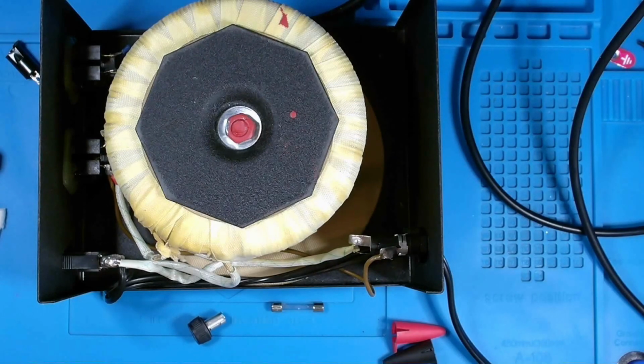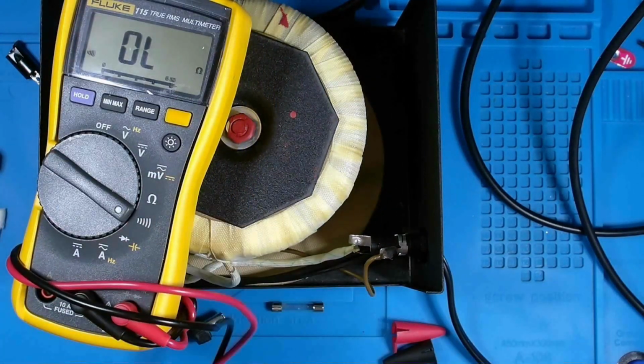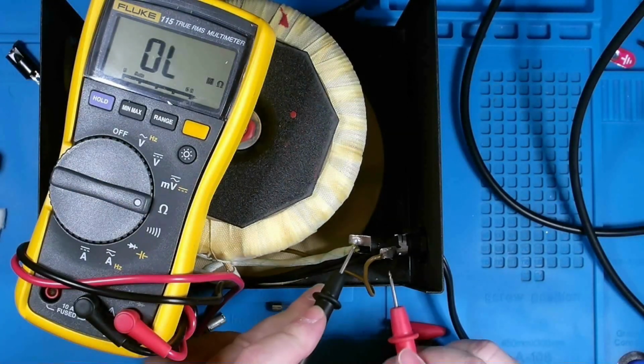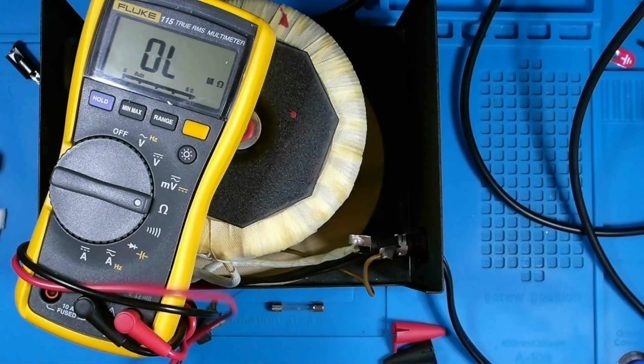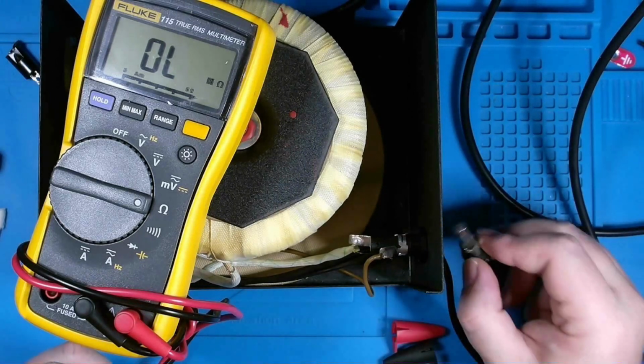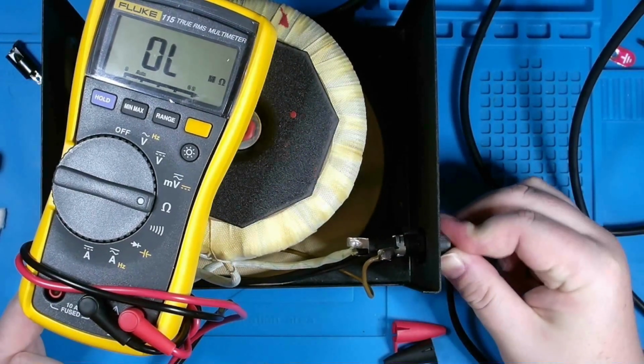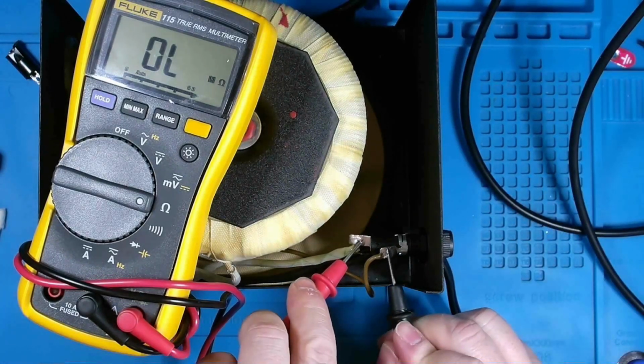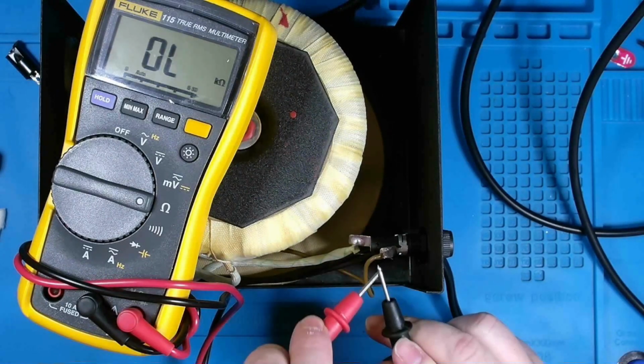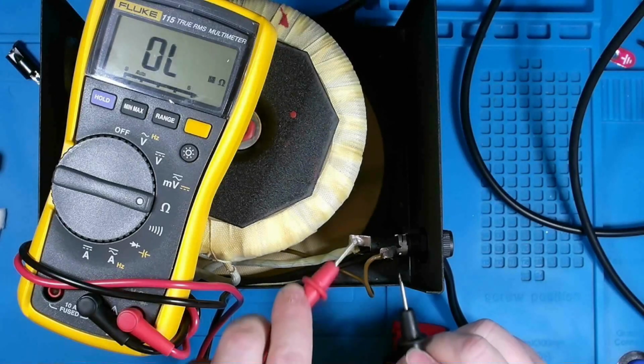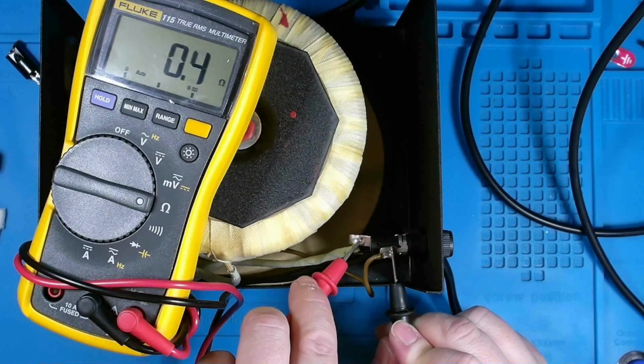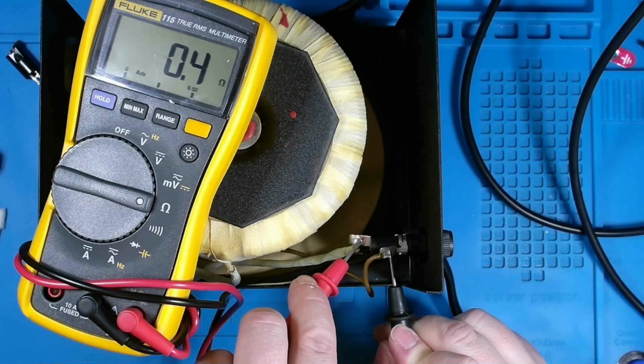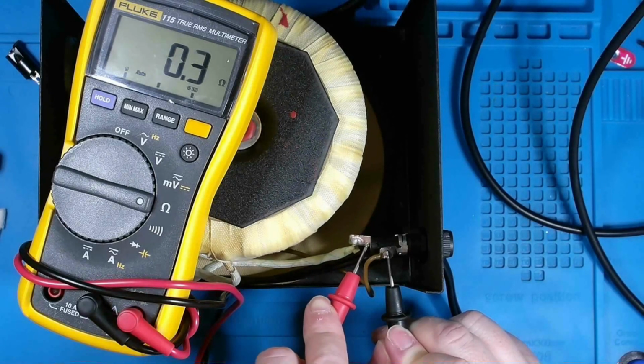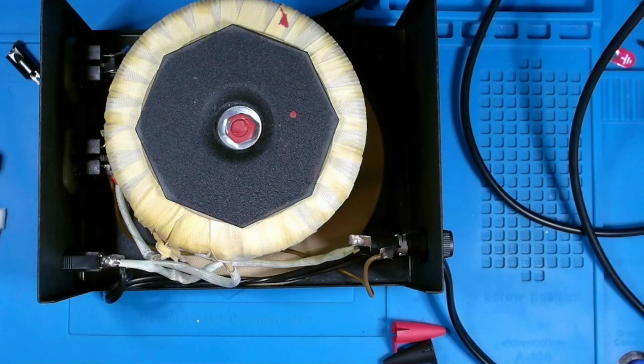But right now, between here and here, it should be open until I put that fuse in, obviously. So let's get that fuse in there, make sure we got good contact. And we do. Yeah, 0.1 ohm resistance on through my leads, so we're about 0.2, 0.3 there. It's perfectly fine. Okay, let me get this put back together and get it plugged in and run through a test again.